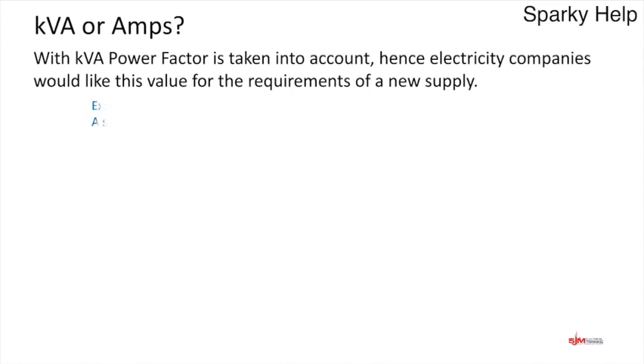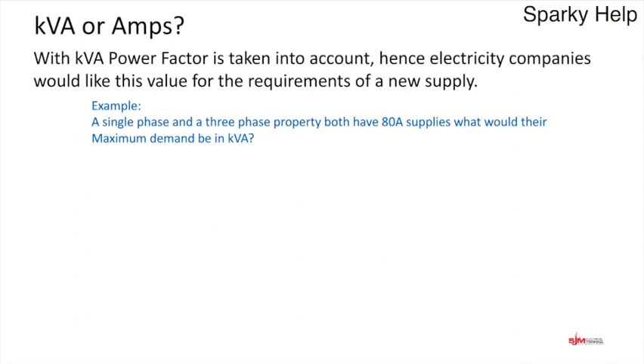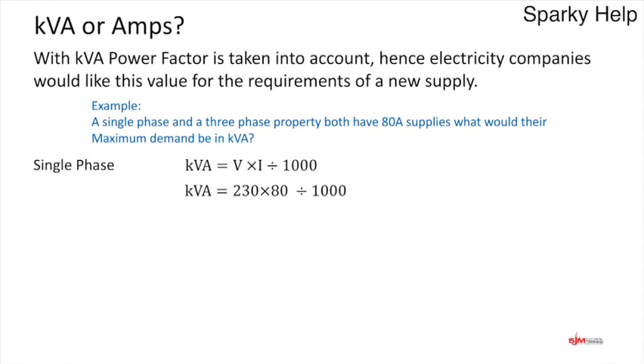So how do we actually work this out? We have a single-phase and a three-phase property, both with 80 amp supplies. For a single-phase installation, KVA is volts times amps divided by 1000 to give us K. So that's 230 × 80 ÷ 1000 = 18.4 KVA. So what you'd write on your test sheet is delete amps and write 18.4.